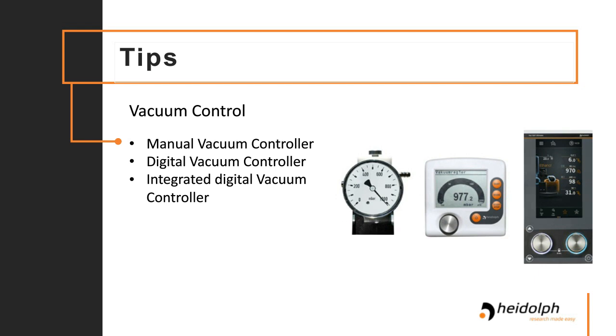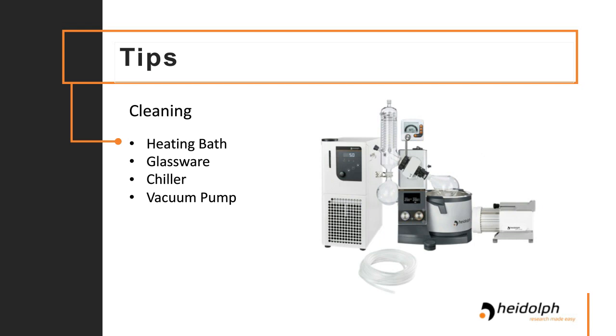Keeping your full rotary evaporator system cleaned and maintained is very important for really increasing the longevity of all the parts of your process. Cleaning your heating bath is important. Sometimes that water can get gross, or you'll see some buildup on the side of the heating bath. I recommend replacing the water relatively often, and when you start to see buildup on the side of your heating bath, I recommend using some alcohol to clean out the sides of it. Or if you get some really bad buildup, maybe heat the bath up a little bit and put a little bit of citric acid in there, rotating your evaporating flask so that there's a little bit of turbulence, and let that sit for about an hour or so.